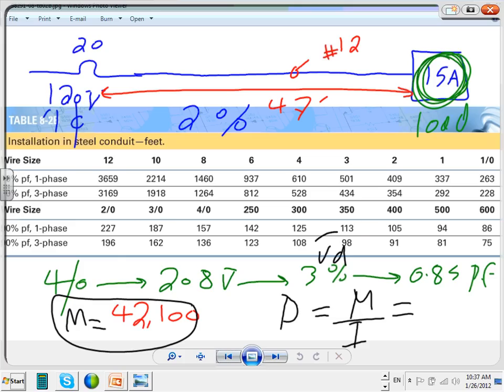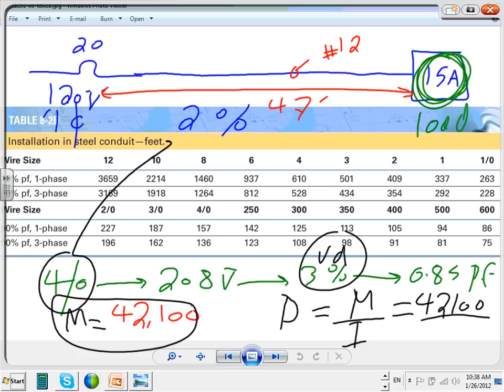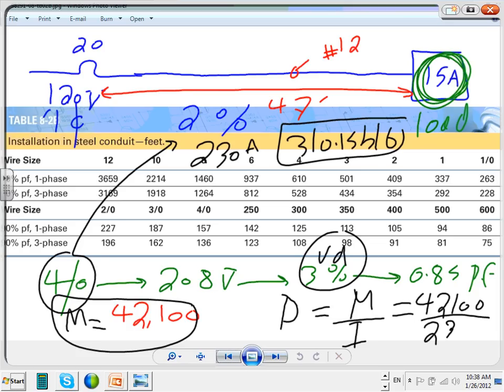This voltage drop, 3%, is for a feeder. Okay, so let's take 42100. Now, this is M. I have a conductor of 4-aught. How much current do you want to carry for 4-aught? Let's use the code. Number 4-aught from the table, guys, can give me 230 amps. This is from 310.15 B16. Okay, divide this by 230. That's how far you can put a panel from the source.